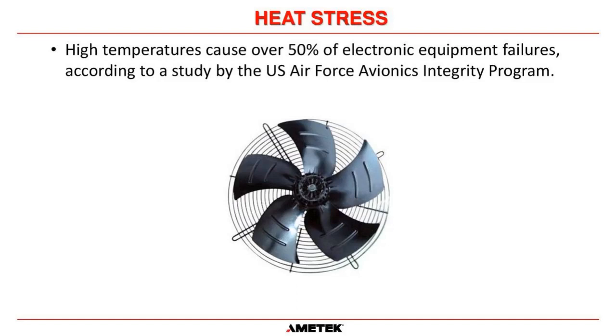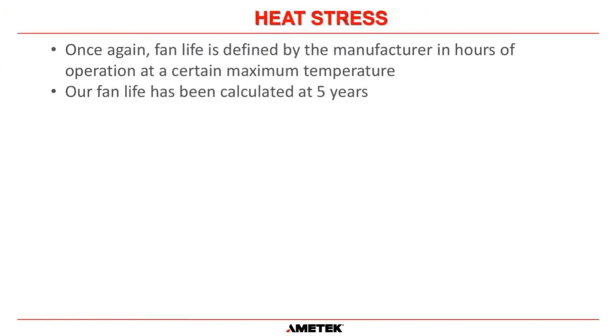So the flip side of that is those fans are relied upon to get the air out, so they have to be maintained. And the fan life is once again defined by the manufacturer in hours of operation. We went to our manufacturers and asked, how long will the fans last? And it was calculated at 5 years if the temperatures stay within the tolerances of the UPS. So that's why we always recommend that the fans are replaced every 5 years. We need to make sure that the fans get the air out of that system.